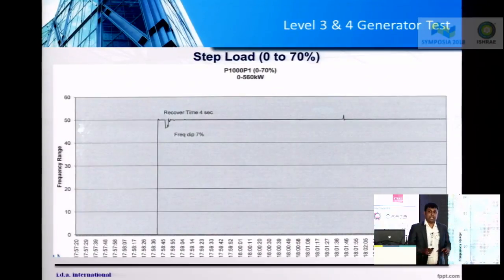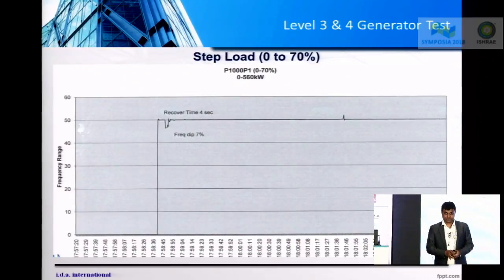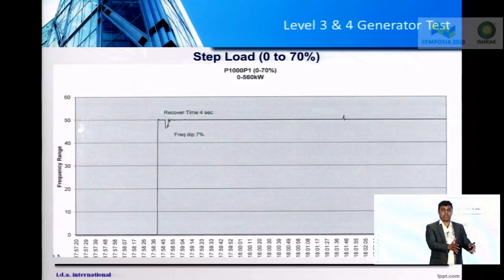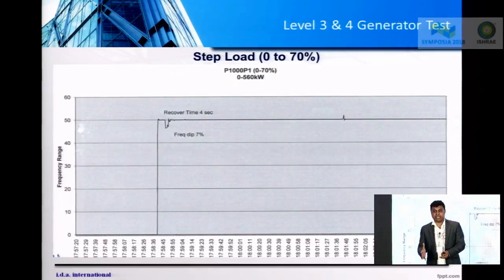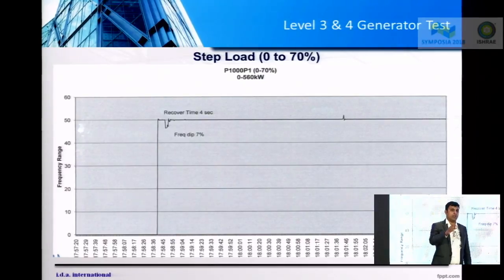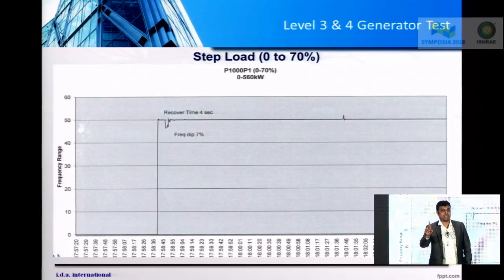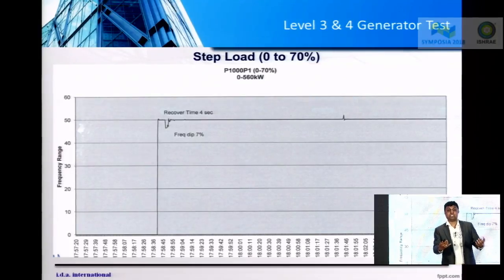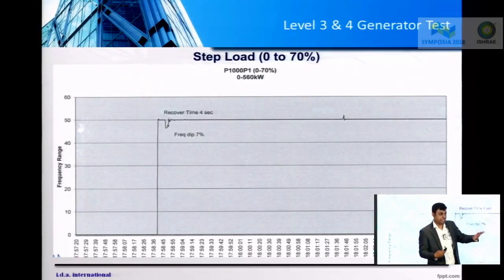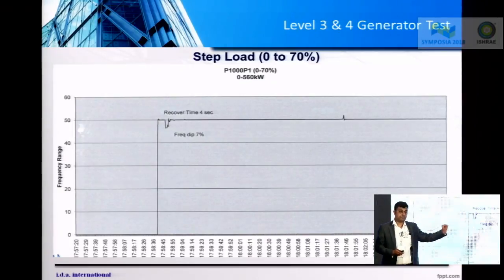Step load test. You might have a very good design. You might have a transformer which is supported by an independent DG. But think of a scenario where the entire load is transferred from transformer to generator in one single step. Normally, if you speak to the generator suppliers, they would say that our generator cannot take more than 70% step load at any given point of time, which means it is important to verify this particular parameter.